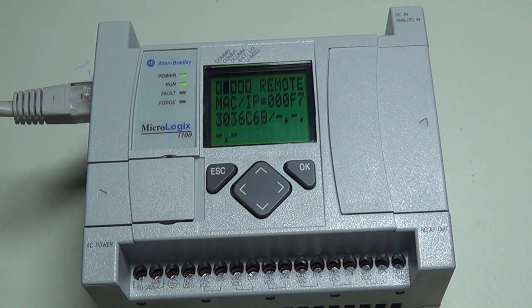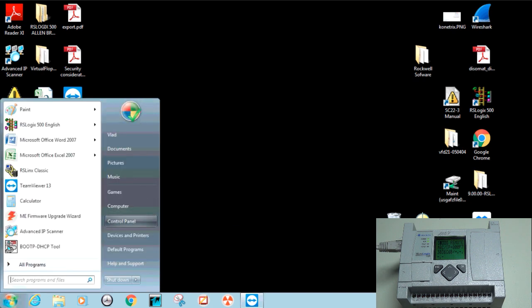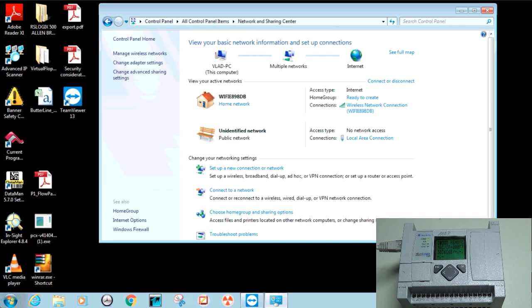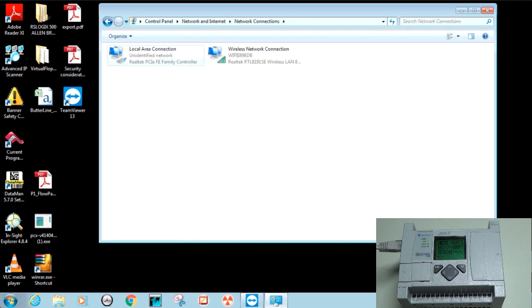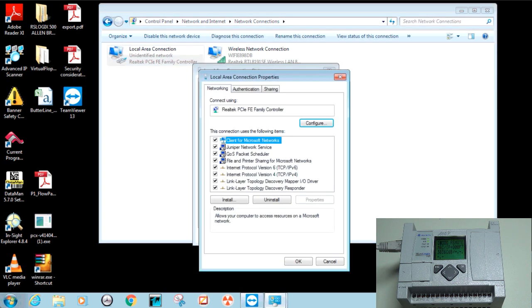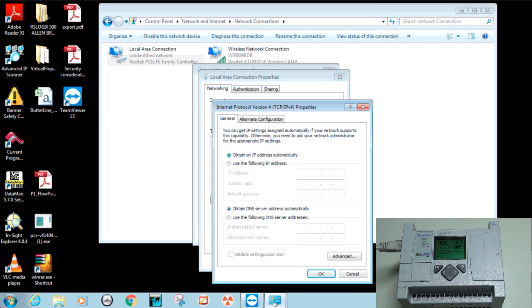The first step in our process is going to the network settings on the computer and making sure everything is configured correctly. Go into Control Panel, navigate to Network and Sharing Center, then Change Adapter Settings. Find the hardware connection, go into Properties, select IP Version 4, and for BOOTP you will need to have 'Obtain an IP address automatically' selected. This allows the physical MAC card on our PLC to set the IP subnet we need to connect to.